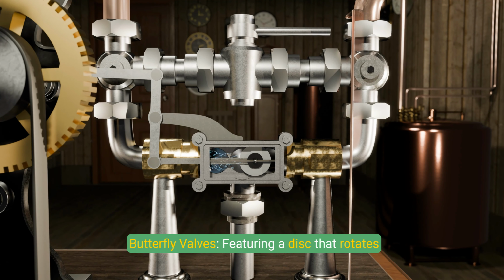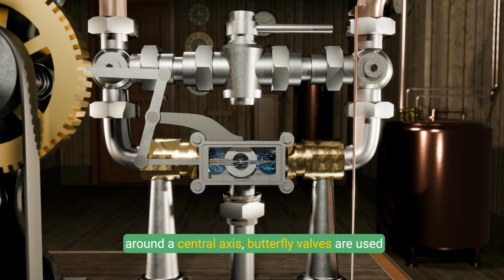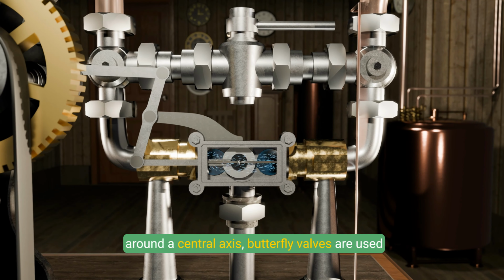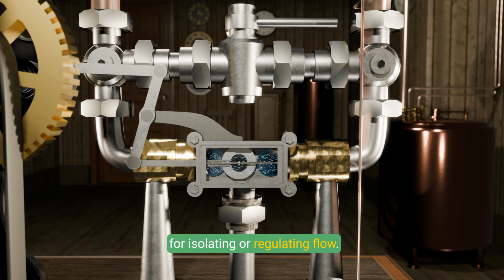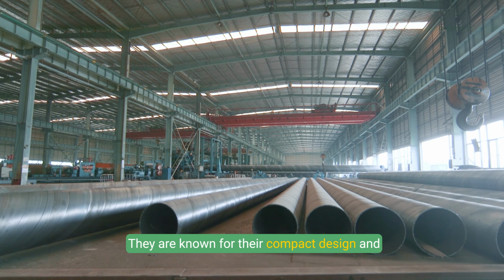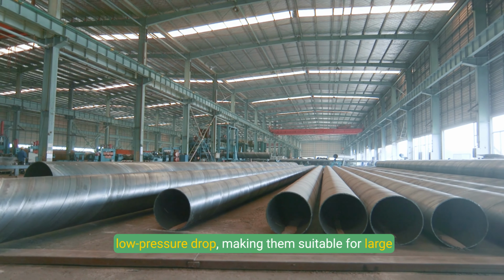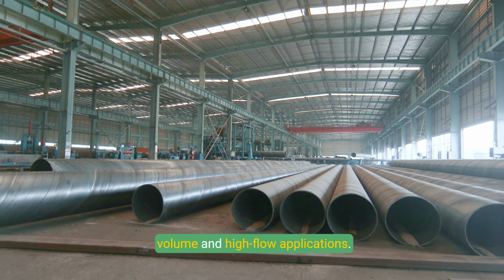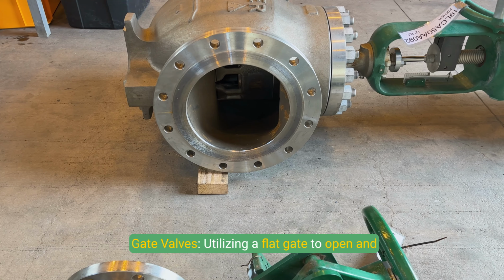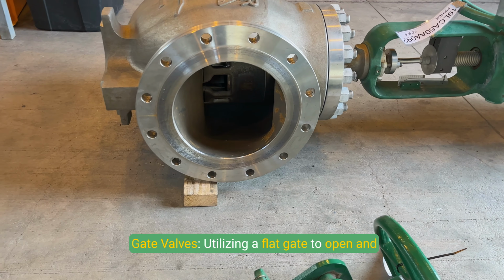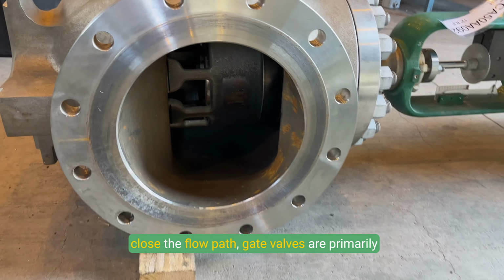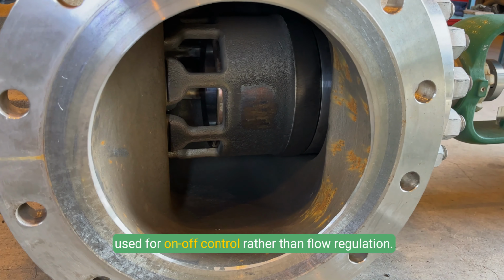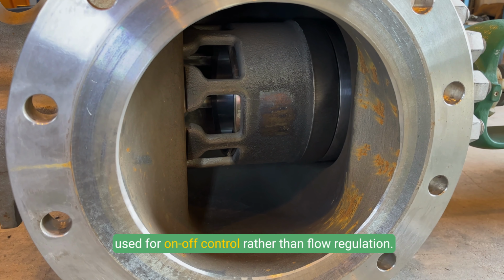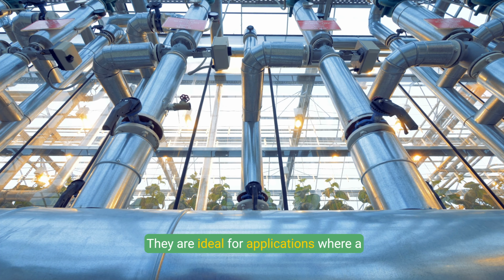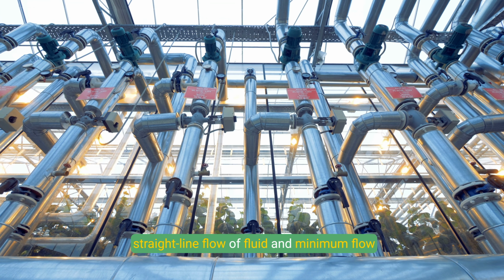Butterfly valves. Featuring a disc that rotates around a central axis, butterfly valves are used for isolating or regulating flow. They are known for their compact design and low-pressure drop, making them suitable for large volume and high-flow applications. Gate valves. Utilizing a flat gate to open and close the flow path, gate valves are primarily used for on-off control rather than flow regulation. They are ideal for applications where a straight-line flow of fluid and minimum flow restriction are needed.